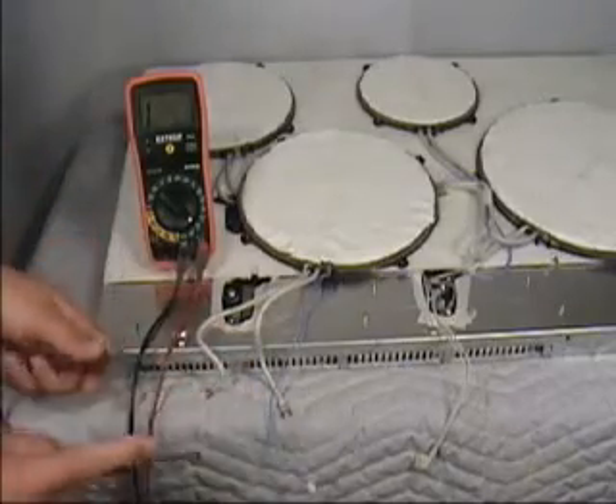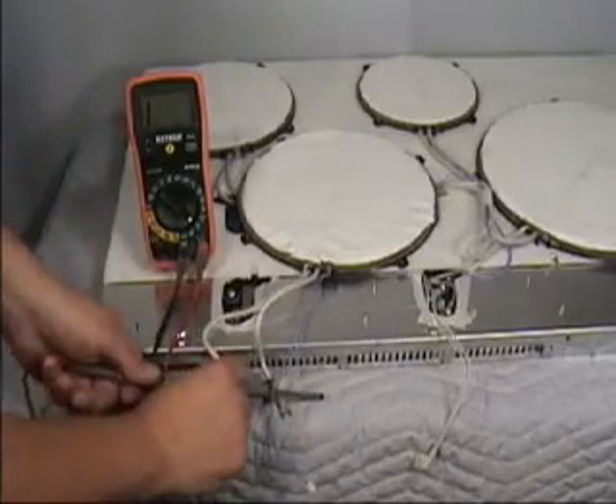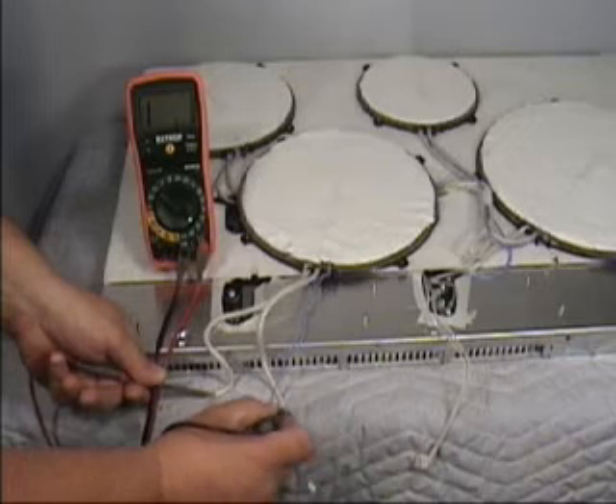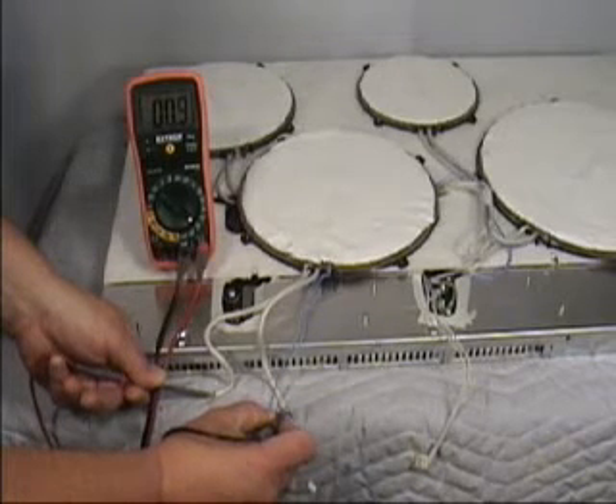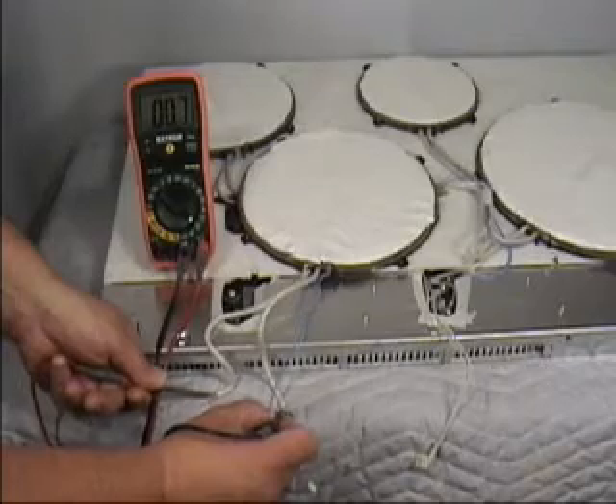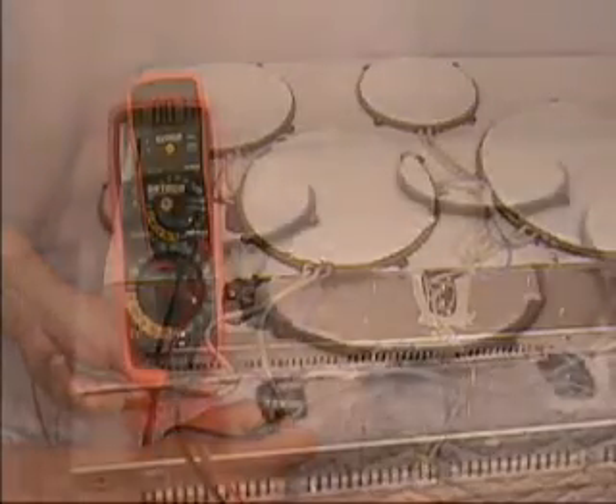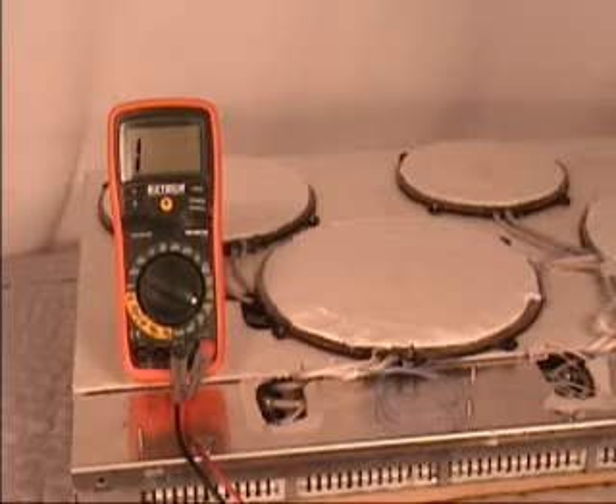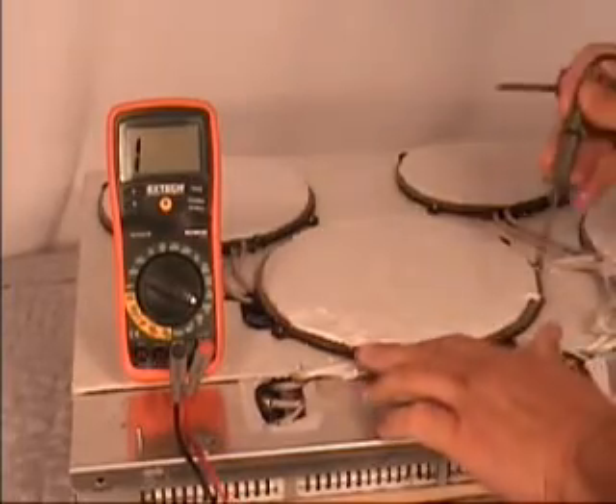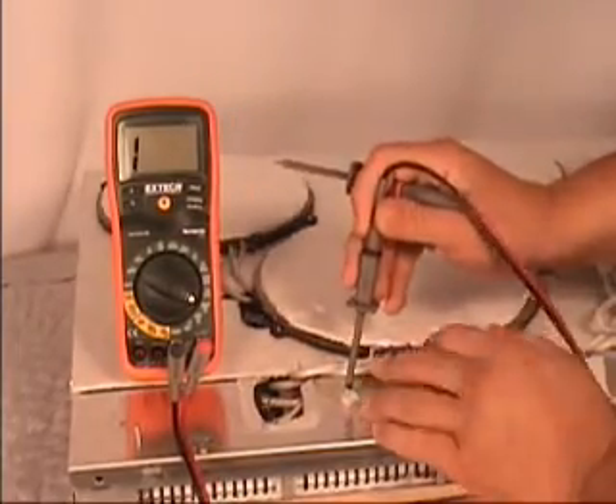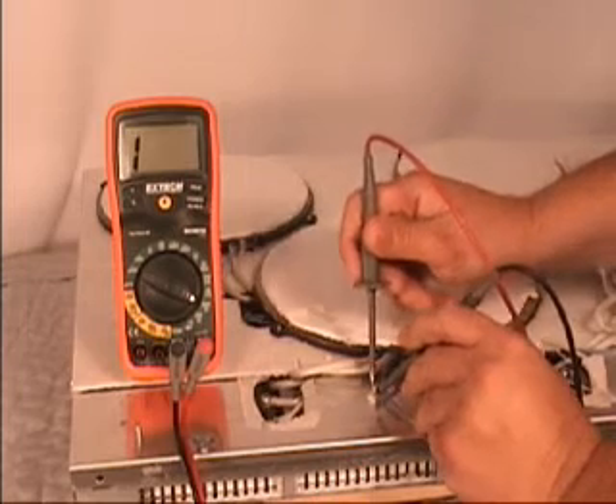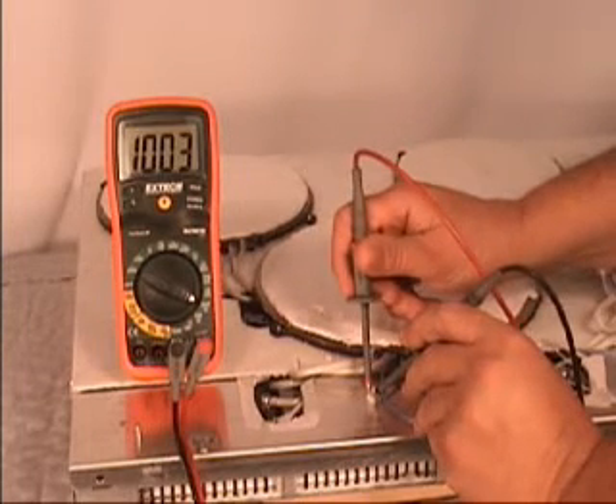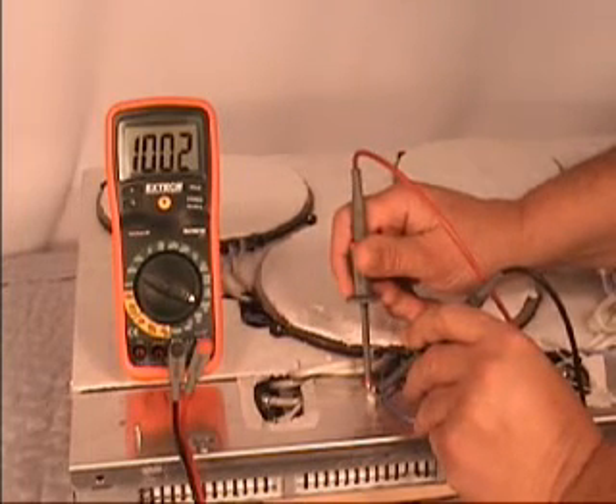To test the coil, use an ohm meter to check for continuity between the 2 forked terminal connectors. The coil should have less than 1 ohm of resistance. Each induction coil assembly has a temperature sensor as part of the assembly. To test the sensor, use an ohm meter to measure the resistance between the 2 wires in the sensor connector plug. The sensor should measure approximately 1000 ohms of resistance at room temperature.